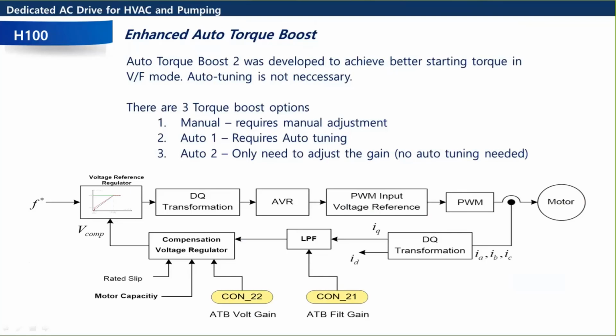And if you guys don't know what an auto tune is, that's entering in all your motor data and going to another parameter and kind of hitting the go button. But then if you're going to do a rotational auto tune where the motor rotates, you got to uncouple your loads. You have to pull off your pulleys or belts and stuff. And people don't like to do that because it's extra work. So they'd rather do something like Auto 2, where you don't need to do any auto tuning. Okay, less work. You just set up one parameter and then you're good to go.